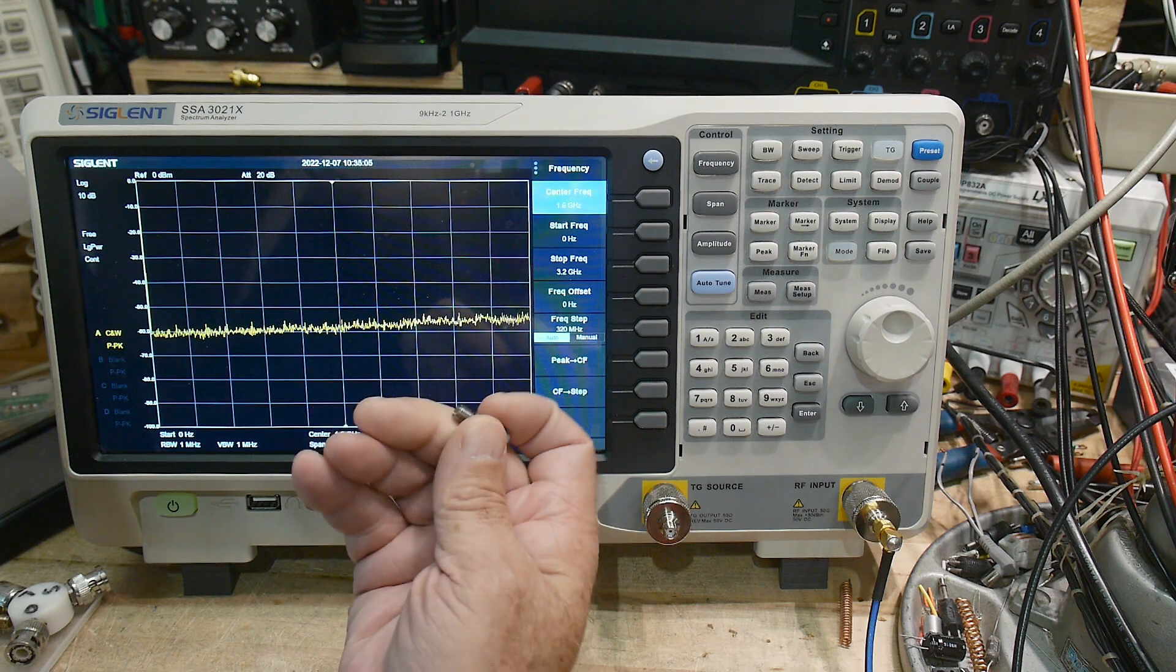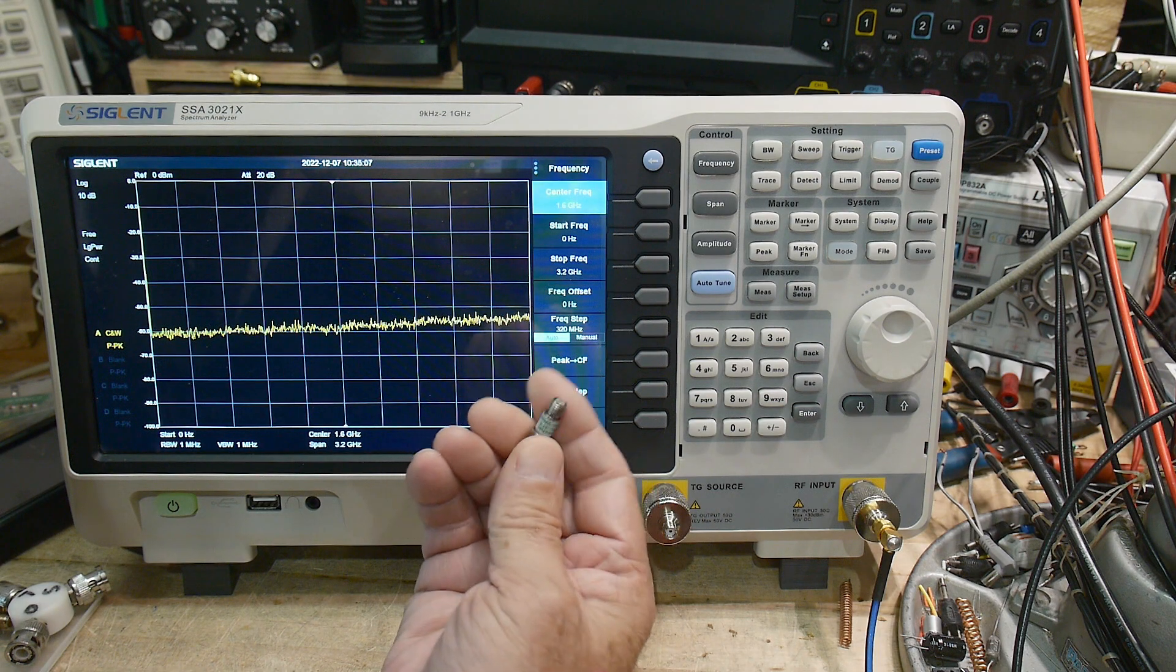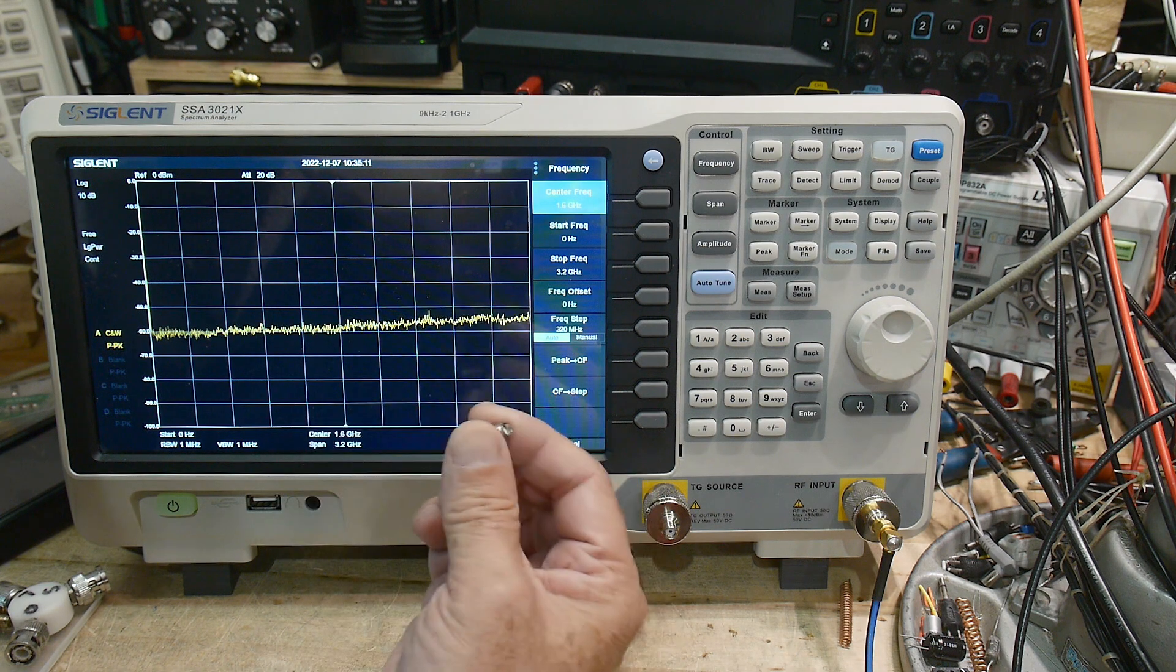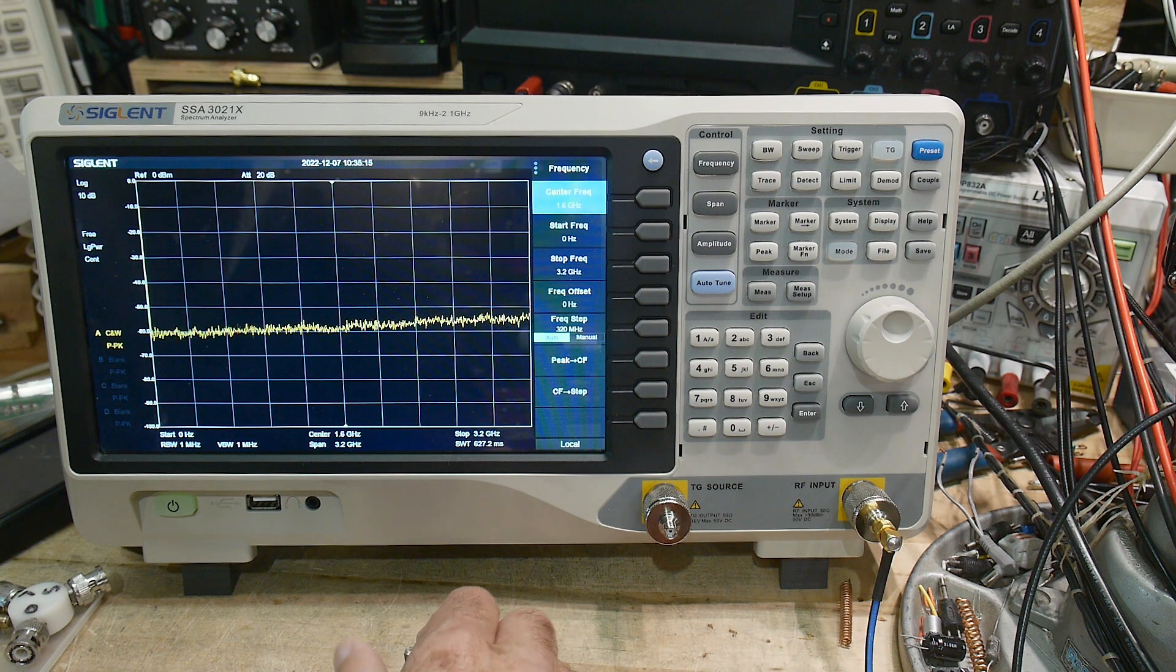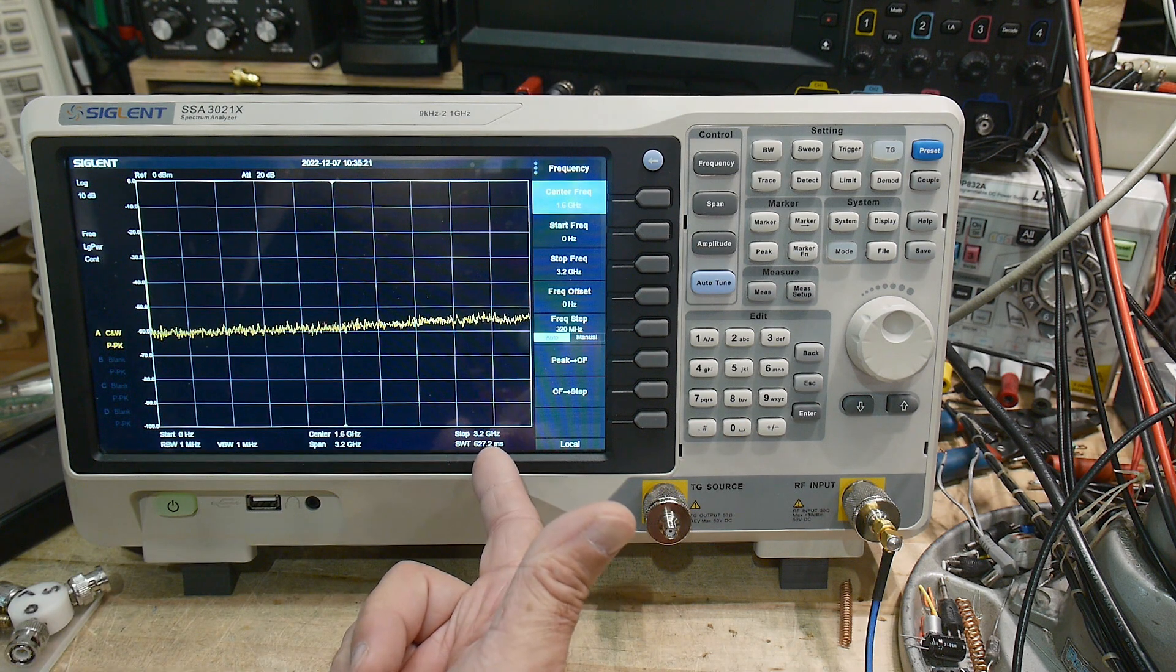I'll get one here. This is a 6 dB attenuator, and it says 6 dB attenuation, but at what wavelengths? You want to see if it's equal 6 dB across all wavelengths, and that's what a machine like this can measure. You need to set the span that you want, and we'll just leave it open. It's going from 0 to 3.2 gigahertz.